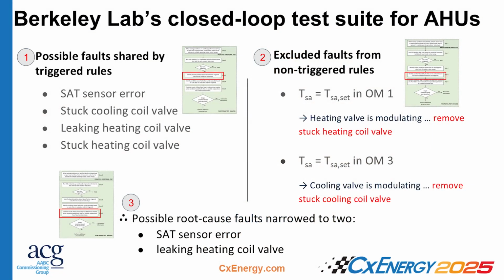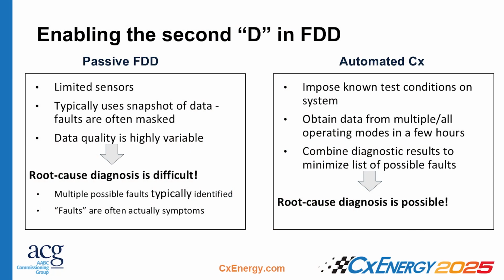So you either have a supply air temperature sensor error or you have a leaking heating coil valve. And now, all of a sudden, running these multiple modes, you're able to dwindle down the number of possible faults and have your response be a lot more targeted, a lot more actionable, running these functional tests. So when we talk about that, we're really trying to enable the second D in FDD, right?